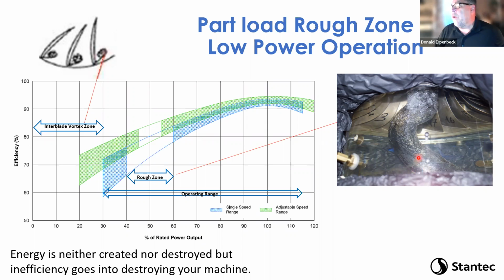So what we do when we go up, every machine does this, we just go through as fast as we can, but we try not to go through it too often. And they went through it in a 1 hour period 4 times, twice up, twice down. And then they were sitting down here at the low power, at below 250 megawatts, which isn't as bad of a vibration regime, but it is a very tough place to operate because of the angles of the flow that happen. And we get little vortexes forming between every blade and the runner as it goes by. So it's a pretty rough regime.